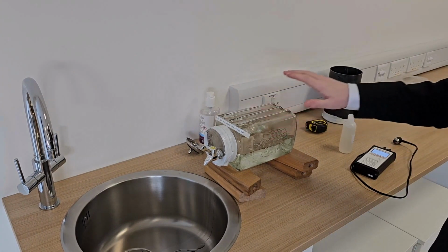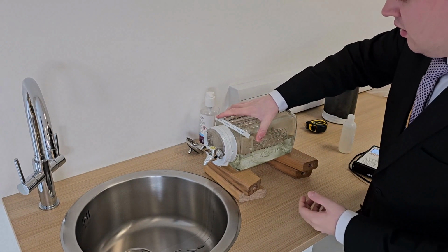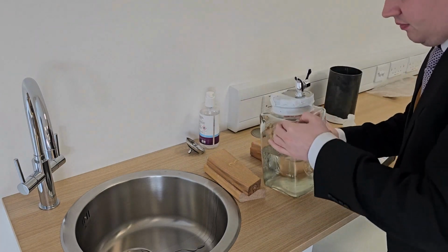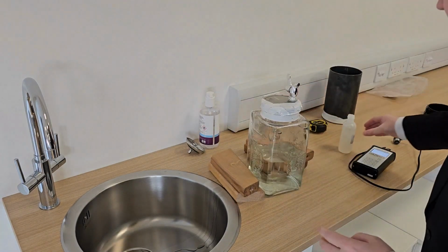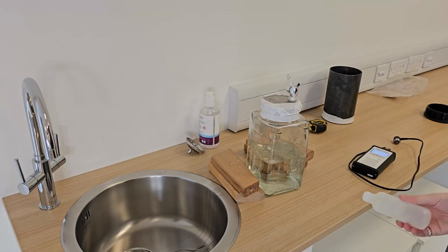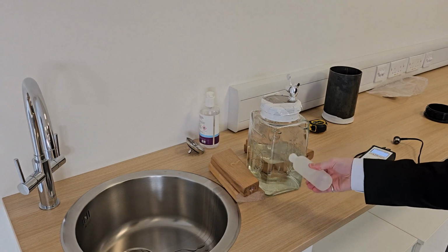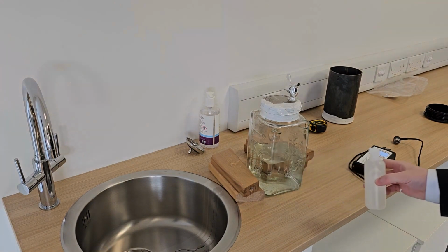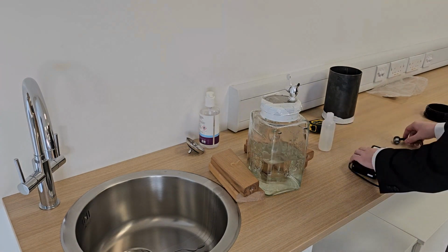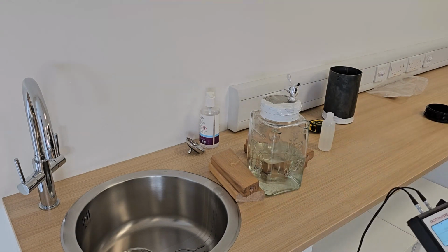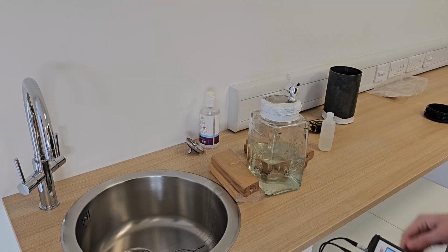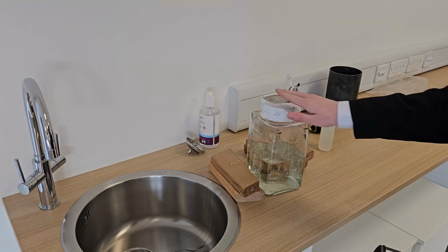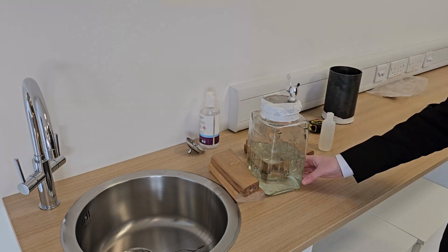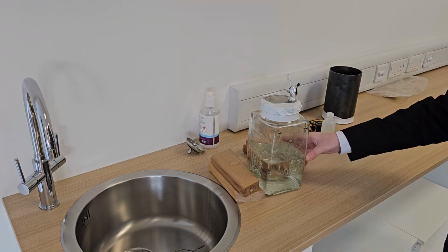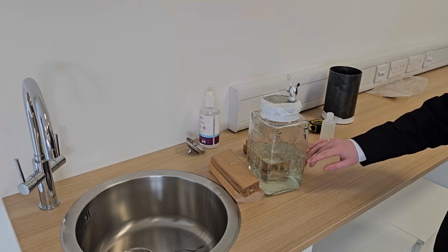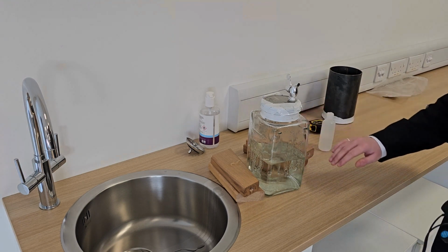Now for a vertical container, the principle is very similar. However, the way we actually do this is slightly different. We can still use the same values as before, or just use the A-scan, but the way we interpret these values will be slightly different. So all I've done now is turn this up onto its end, so we now have a section of essentially a completely full pipe until about halfway up, and then a completely empty pipe for the rest of that.